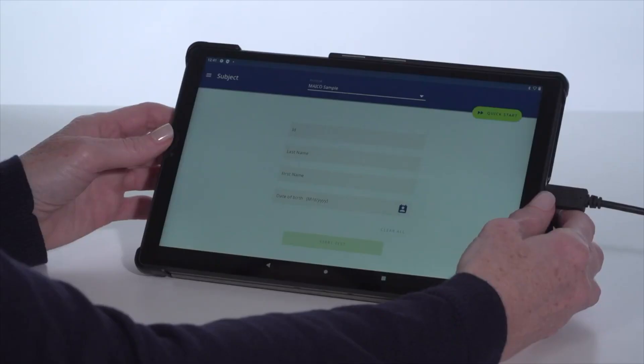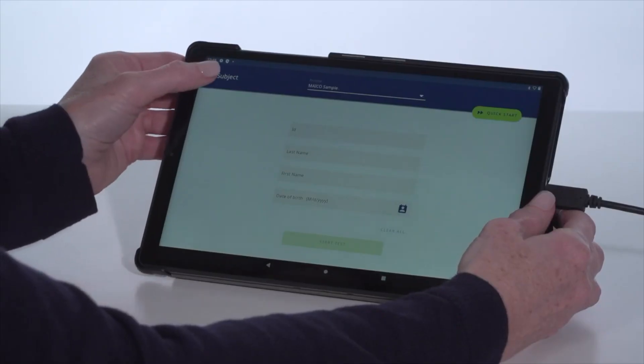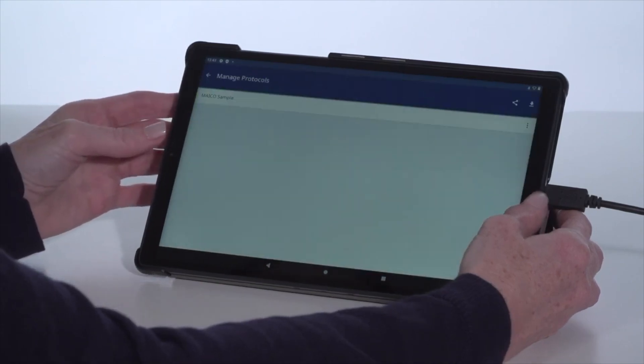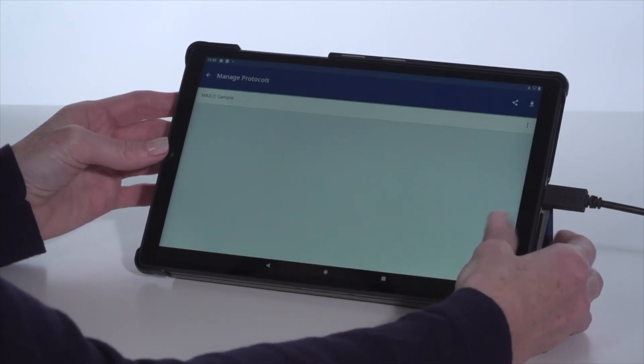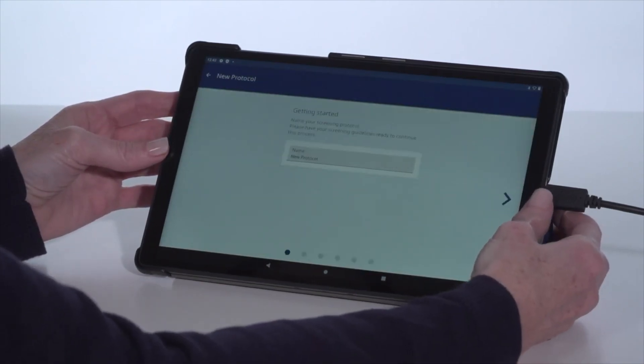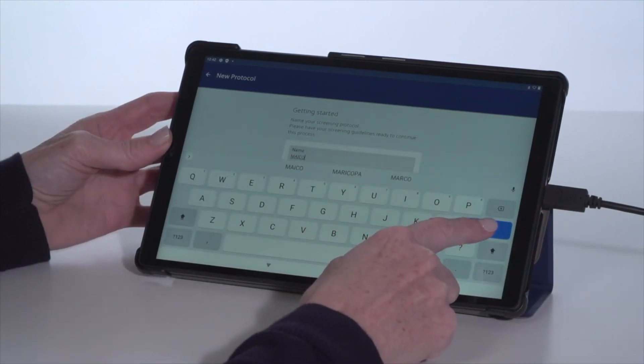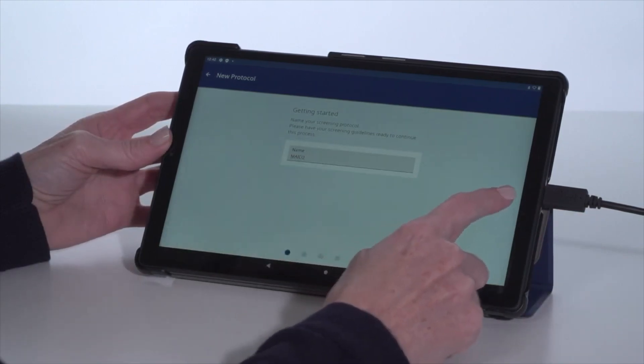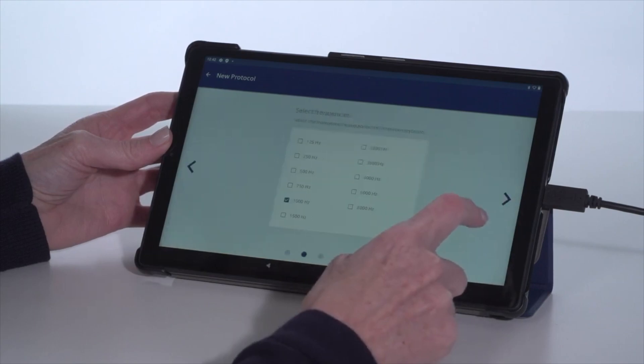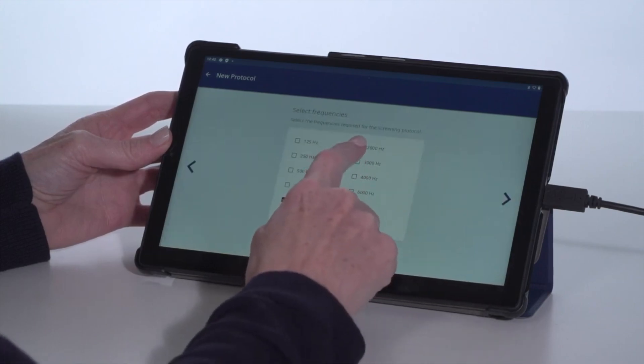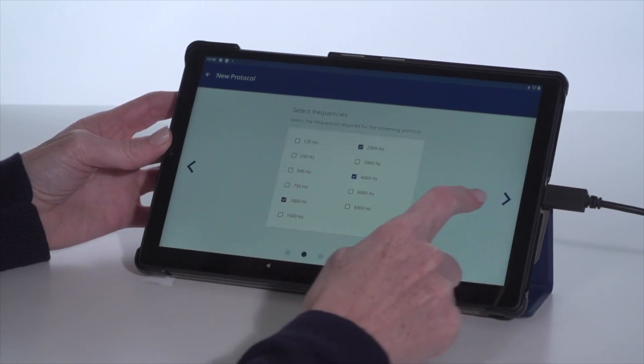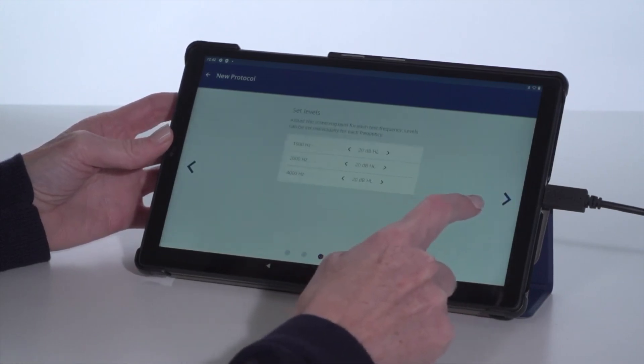Although a default protocol is available to perform a hearing screening, one of the key features of this app is the protocol creation wizard. The protocol wizard walks through each selection so a user can be confident in the setting. This allows the device to be set to the specific screening guidelines of the location.